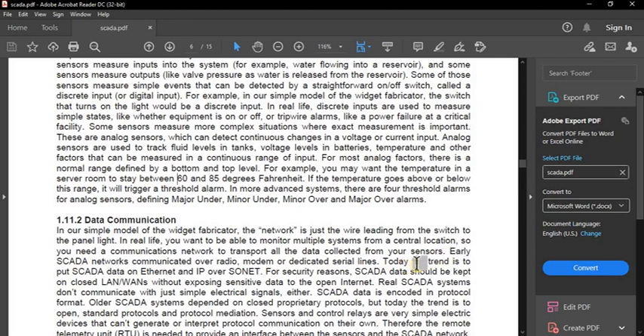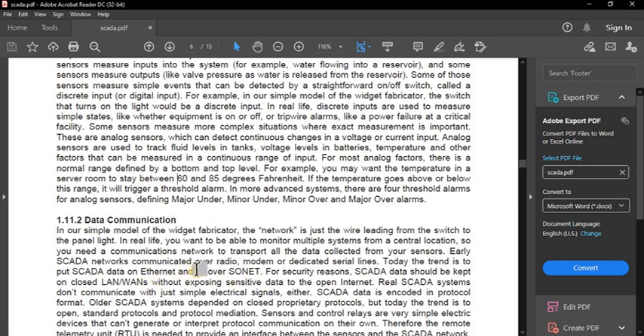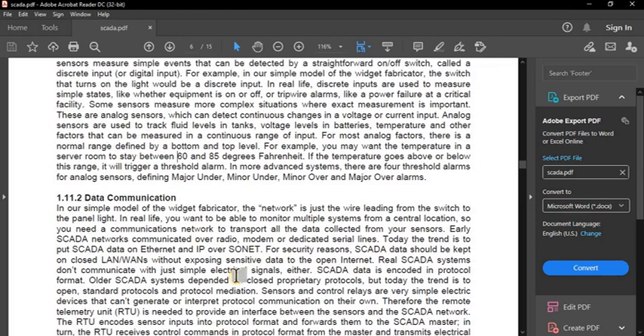Sensor data is given to the data communication port. Early SCADA networks communicated over radio, modem, or dedicated serial lines. Today the trend is to put SCADA data on Ethernet and IP networks. For security reasons, SCADA data should be kept on closed local access networks or wireless access networks without exposing sensitive data to the open internet.